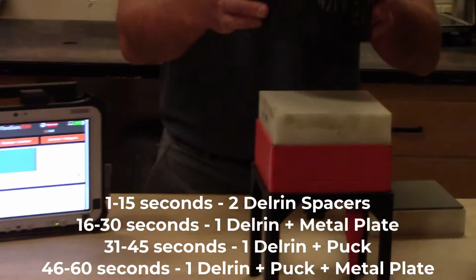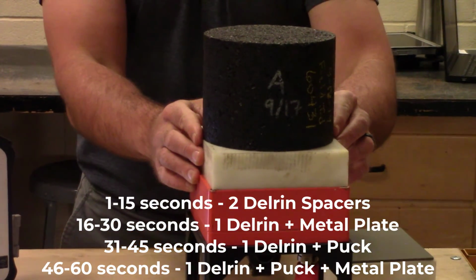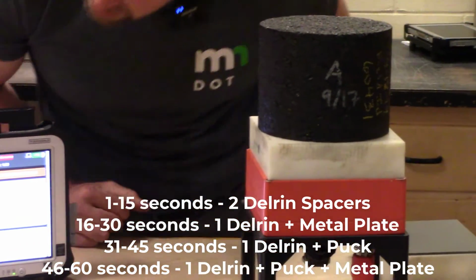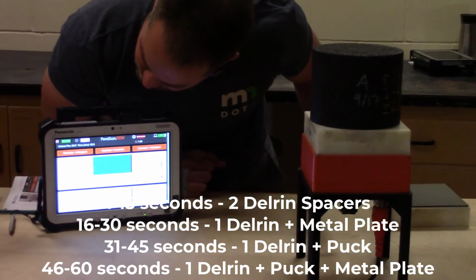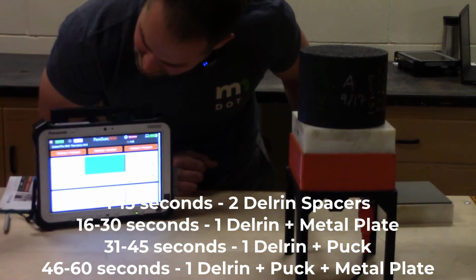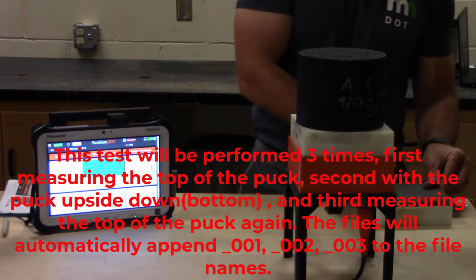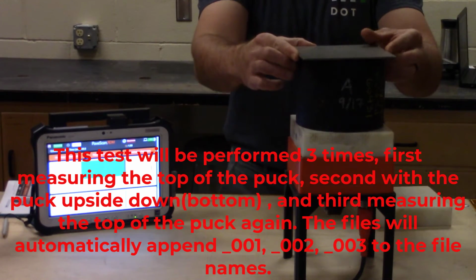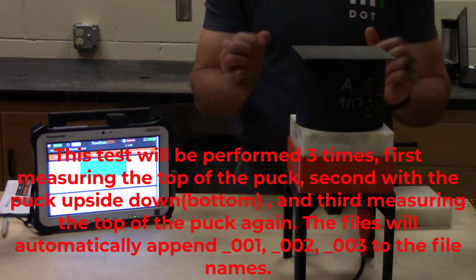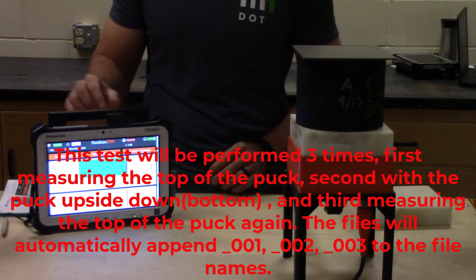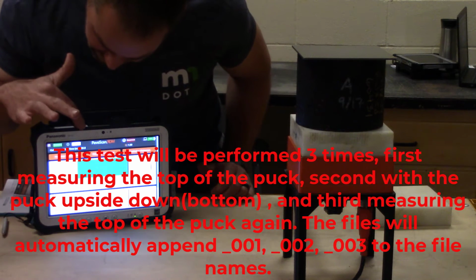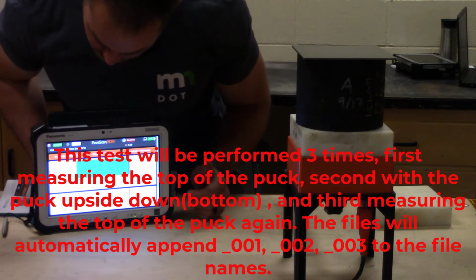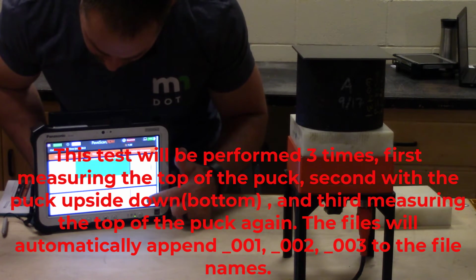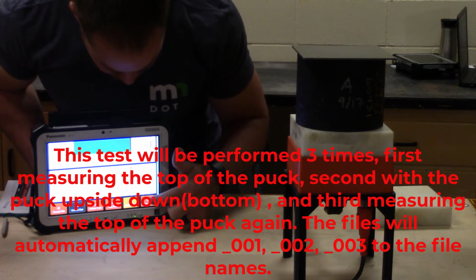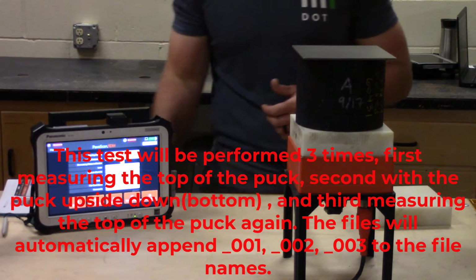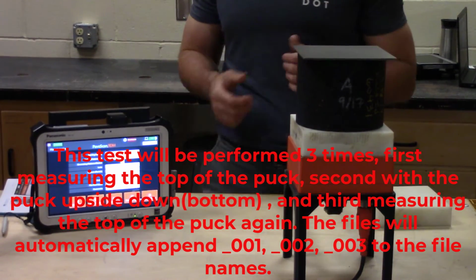So after it hits 30 seconds, now we're going on to the puck testing portion. And once that hits 45 seconds, then we're going to move to the metal plate on the top side portion. And this is going to complete our measurements. Once this hits 60 seconds up here, we're going to be able to scroll down and just stop collecting. And at that point, you've collected all the necessary information you need to be able to extract dielectric from the puck.